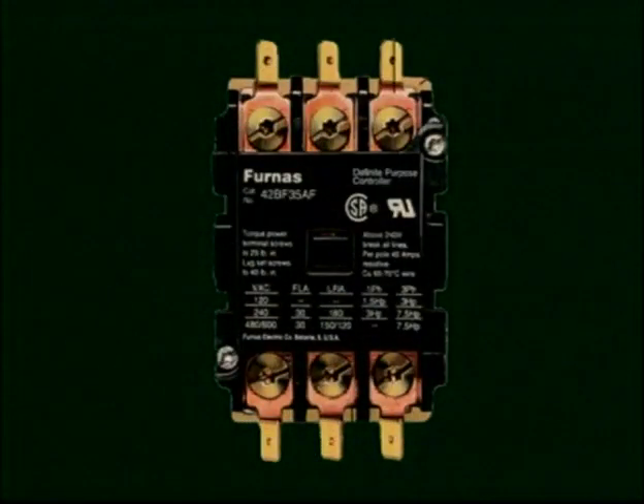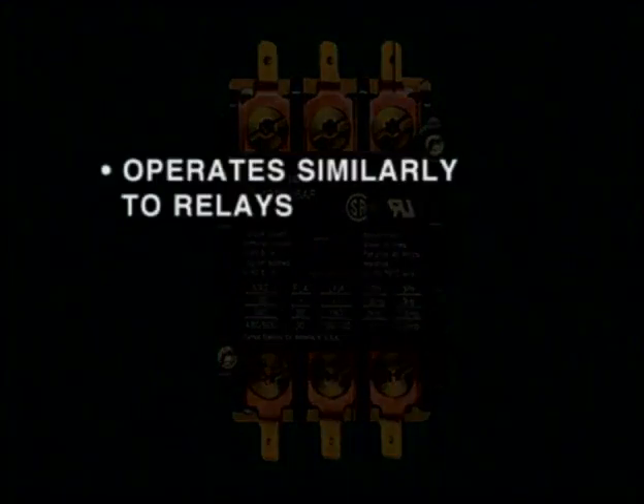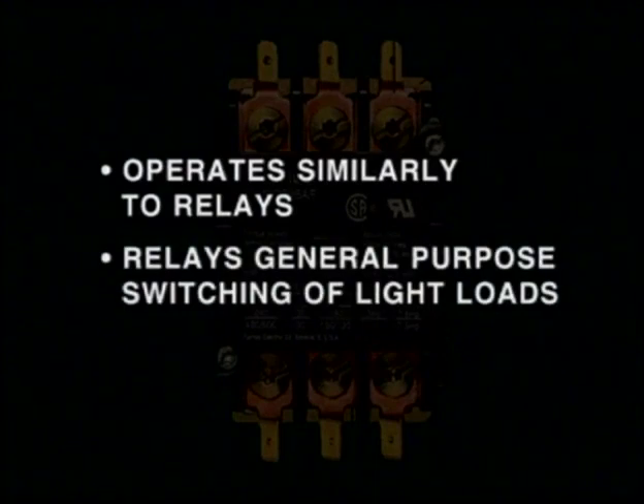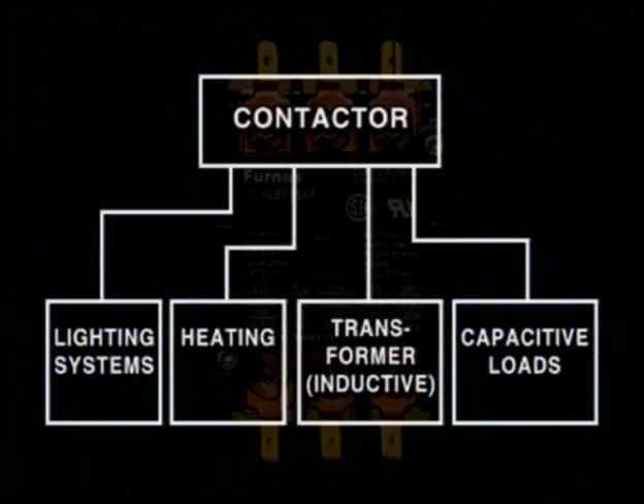Magnetic contactors, as the name implies, also actuate their contacts by energizing a magnetic coil. In fact, contactors operate in a very similar fashion as control relays, except that relays are used for general-purpose control switching of light-duty loads, while contactors are used for the switching of lighting systems, heaters, transformer loads, which are inductive, and other capacitive loads.